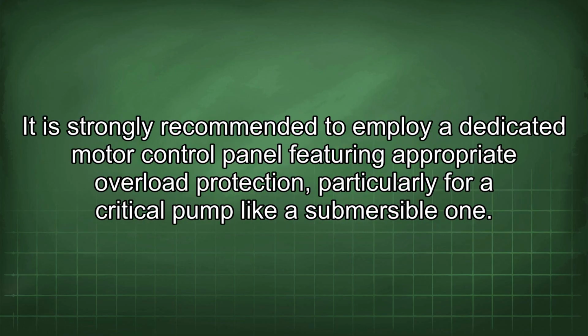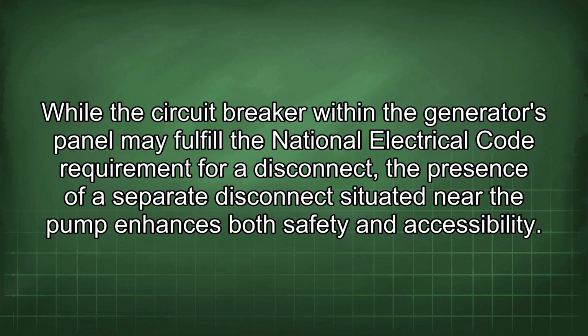It is strongly recommended to employ a dedicated motor control panel featuring appropriate overload protection, particularly for a critical pump like a submersible one. While the circuit breaker within the generator's panel may fulfill the National Electrical Code requirement for a disconnect, the presence of a separate disconnect situated near the pump enhances both safety and accessibility.